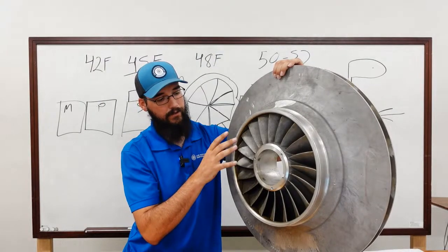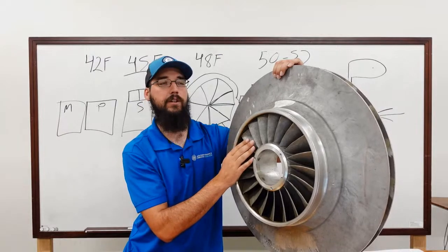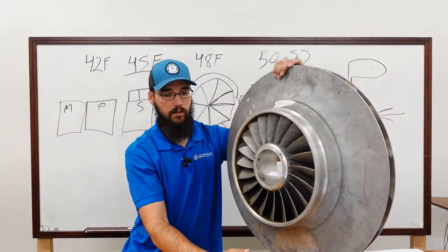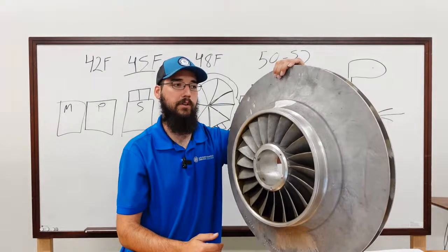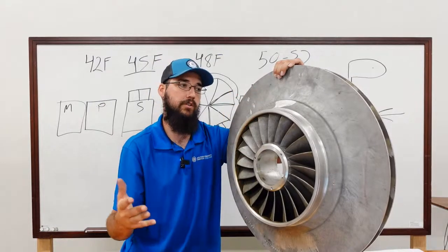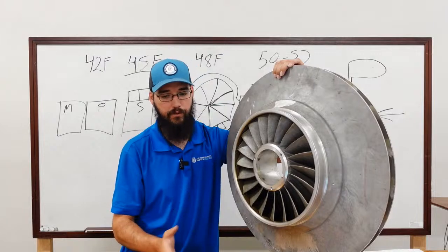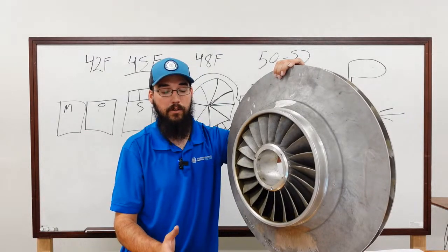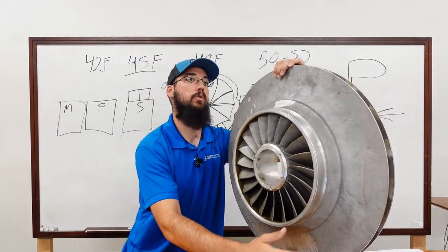That is, in its core function, what a surge is. And the reason we stop surging is because the surge is literally lowering the lift. So your lift drops because you're no longer moving refrigerant, and because it's actually able to reverse flow, it essentially slightly begins to equalize the refrigerant, which is what you needed to have happen in order to drop your lift and allow the machine to return to normal operation.